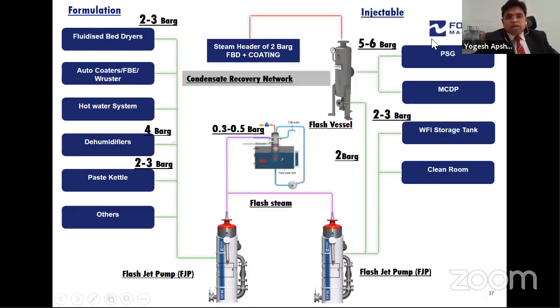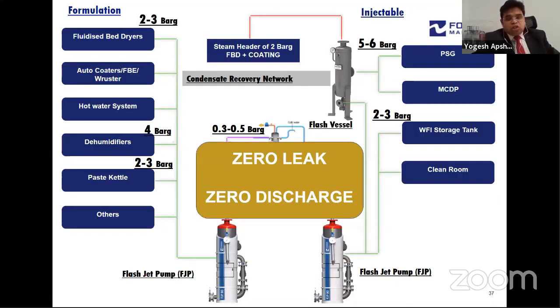Similarly, on the injectable side, for the pure steam generator and the MCDP or WFI stills, which require steam at a higher pressure, we have flash vessels which can give steam at a lower pressure of 2 bar gauge. We can use that steam for sanitization, sterilization, tank sterilization applications, WFI storage tanks and clean rooms. If you recover all this condensate, you will definitely have a zero leak and zero discharge plant.